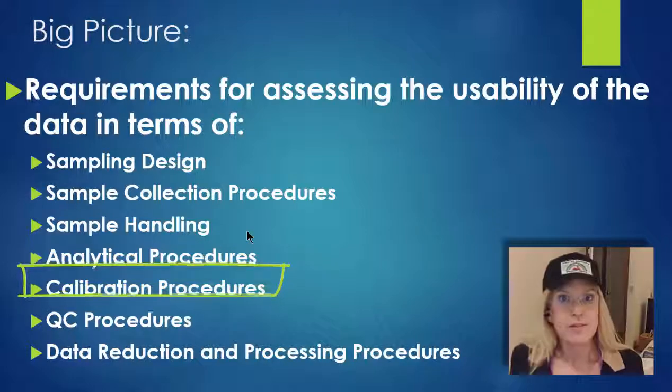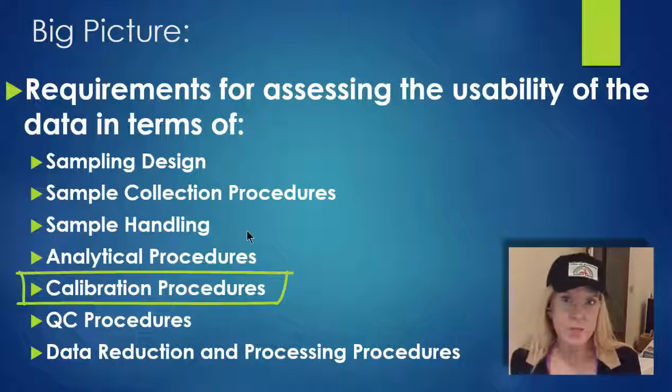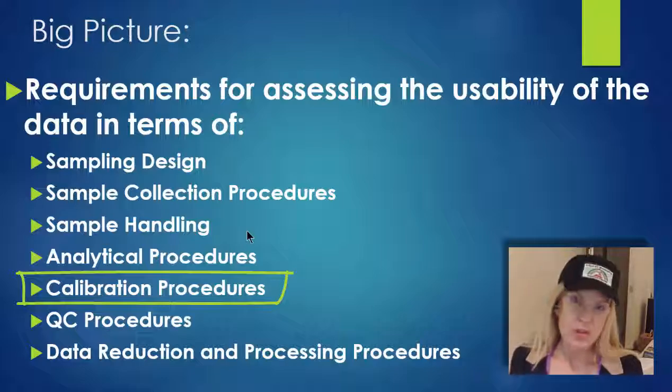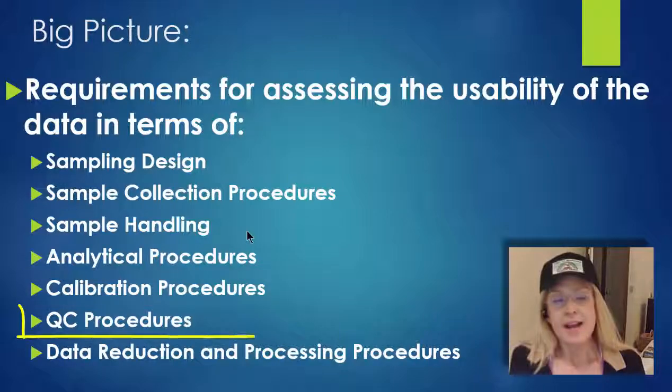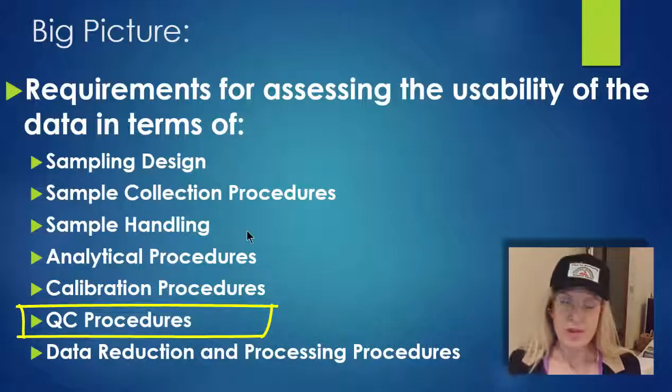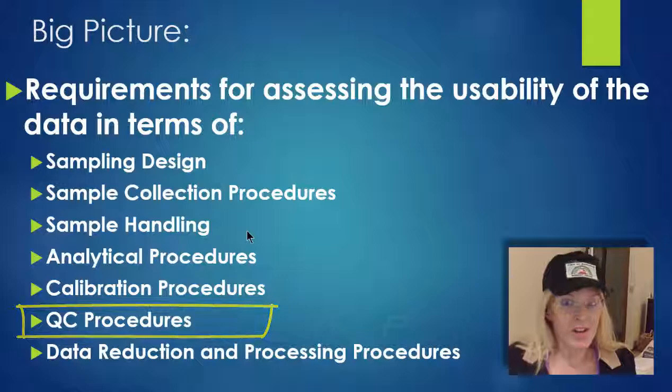Calibration procedures, instruments that are out of calibration, and usually that's after 12 months since the last calibration, but for whatever it is for your measurements, you make sure that you ask the question, is it within calibration? And then QC procedures, you have to do some sort of check of something during the project. Flow rate, temperature, pressure, those can be easily compared to handheld standards. There's excellent companies online with really cool instruments that aren't that expensive.